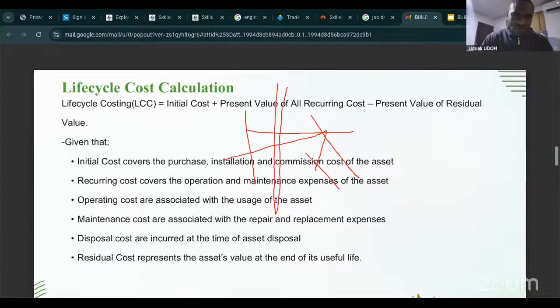You may ask, why would there be need for commissioning an AC on site? Why is a cost attached to it? There could be need to top up the gas, the refrigerant in there. Some comes in a standard volume, but since production is always in bulk, there could be need to top up the gas. It's not that there won't be gas in there, or that the gas won't serve, but after using the manifold gauge, did the refrigerant level meet the standard for that unit to operate efficiently?